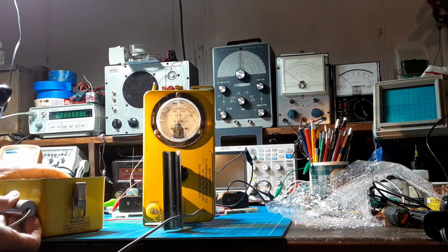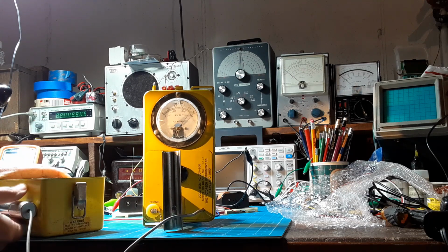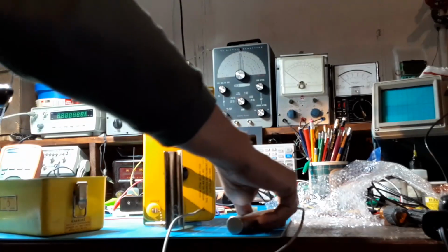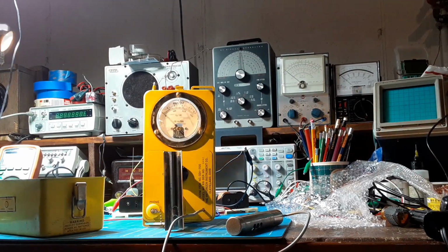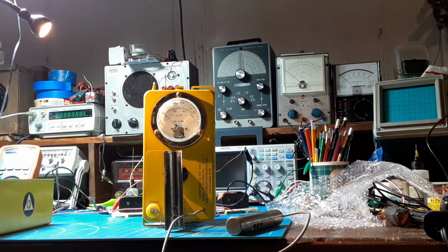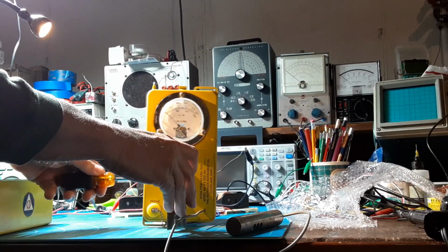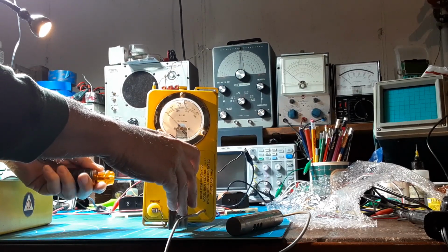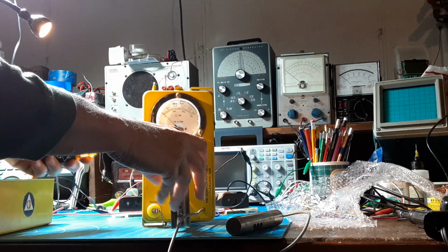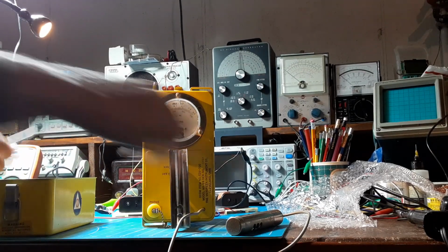When we put it there, you see we're way up. So, well, of course, it's got to kind of set to itself, but it's coming down a little. All right, so that should be 2. So what we got to do is change the calibration on it. And that's on the side here where we did the high voltage calibration. So I'm going to turn that down some, just to kind of get closer to a ballpark. Okay, that's all the way counterclockwise, and we'll see what that does.